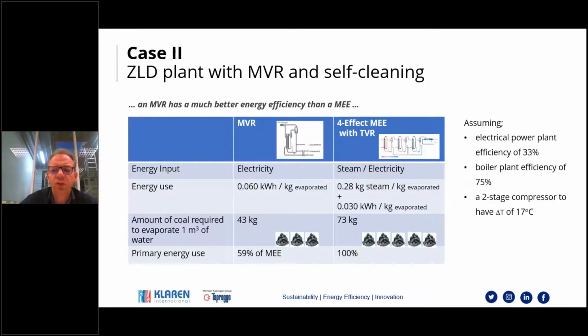If we then convert those both energy uses to the amount of coal that you would need to evaporate 1 cubic meter of water, you would get to 43 kilo of coal for the MVR plant, and almost double for the MEE. So you can directly save 40% of your prime energy input, and that's of course very much wanted. Although we do realize that in some places of the world and some applications and plants, the availability of steam is there, which makes it attractive to use that, sometimes even waste steam, and not to choose the MVR.